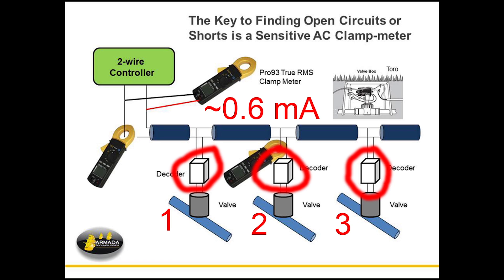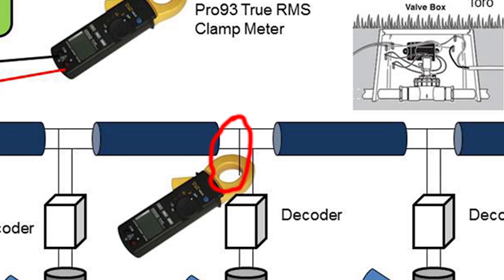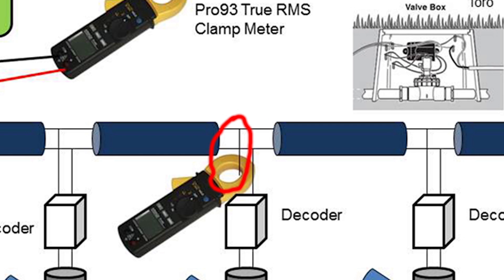As you test, as we see here in the third Pro93, you're going to test on one leg of the two-wire system wiring that comes into the decoder. You don't want to test both wires because it tends to cancel itself out—you get zero for a reading. So you're going to test on one side and take a milliamp reading on the inbound of that decoder.